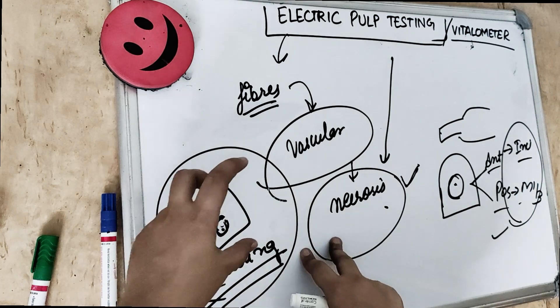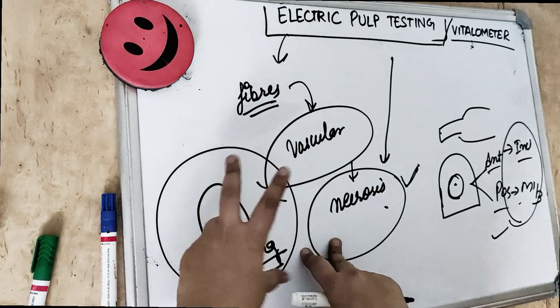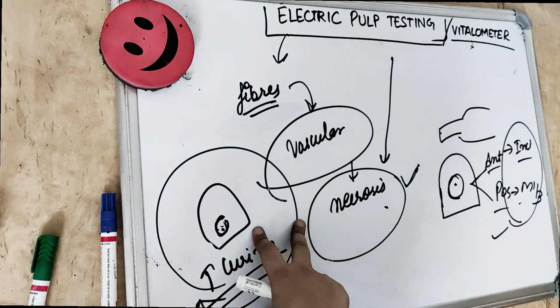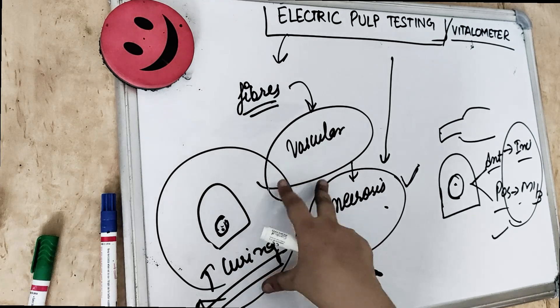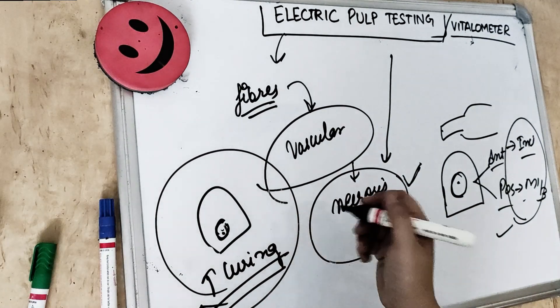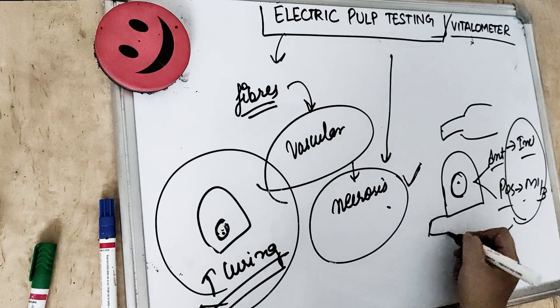The patient is asked to hold the metal handle or lip clip to complete the circuit. We ask the patient to release their hand when they feel a tingling sensation or pain, to stop the test. Releasing the hand itself stops the current. We should avoid the electrode tip touching any metallic restoration.